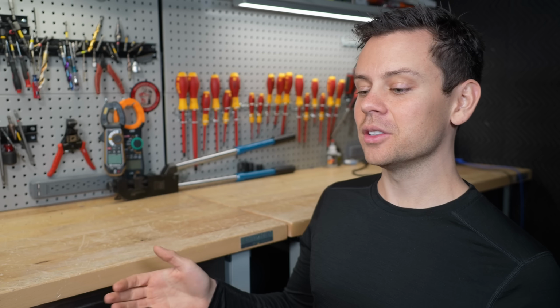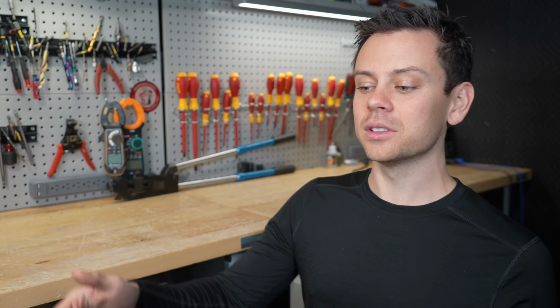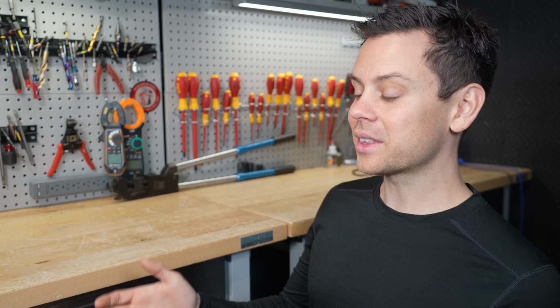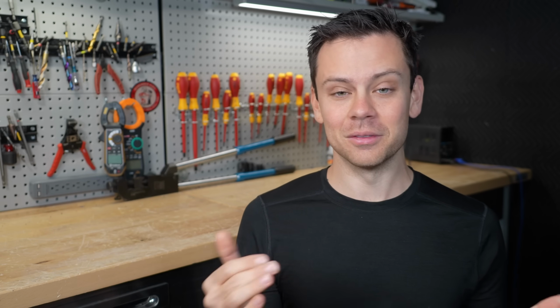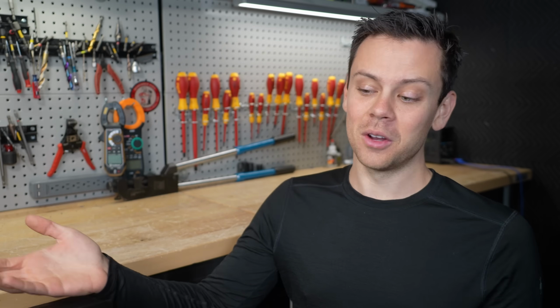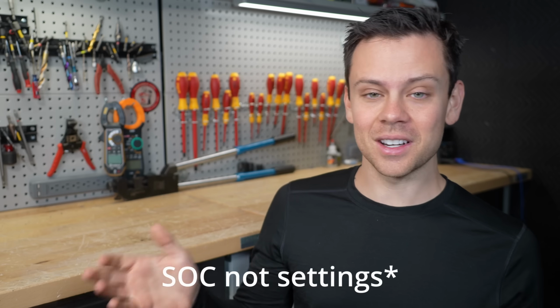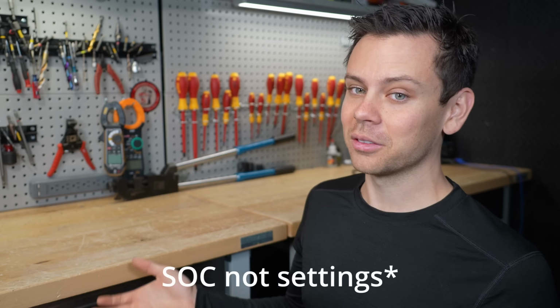Next, whenever it cycles, it doesn't use the capacity that it tested on the last cycle for the new cycle to communicate to the inverter when you have closed loop communication. So what that means is your battery is going to cut off from voltage and not from capacity. So if you're trying to cycle with capacity, it's not going to be accurate. And that's a pretty big problem if you're using these with hybrid inverters, which if you have closed loop communication, I'm expecting you probably do. The SOC is not going to be accurate. This is a software problem.